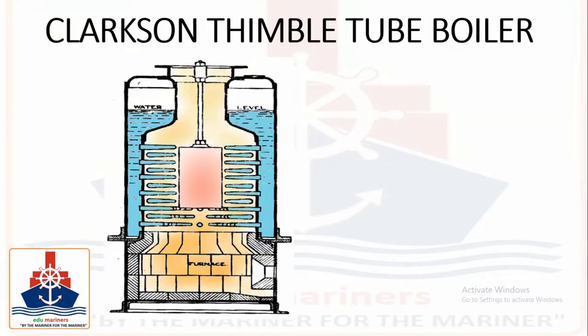The basic form of the boiler consists of an outer shell enclosing a cylindrical furnace, surmounted by a combustion chamber into which the thimble tubes are projected. These thimble tubes, which you can see here, are expanded and bell-mouthed into a cylindrical tube plate forming the combustion chamber.